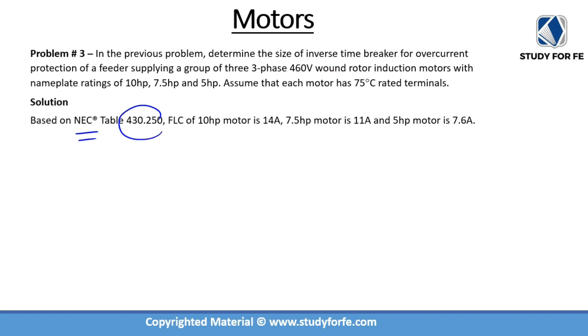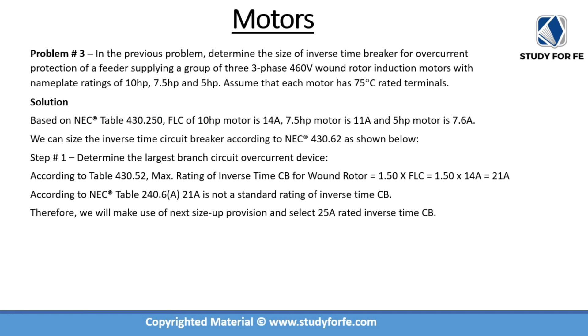Based on NEC table 430.250, FLCs are: 14 amps for the 10 horsepower motor, 11 amps for 7.5 horsepower, and 7.6 amps for 5 horsepower. Per NEC 430.62, this is a two-step process. Step 1 involves determining the largest branch circuit overcurrent device, which we did in the previous problem — it is 25 amps for the 10 horsepower motor, determined using table 430.52 and table 240.6(A).